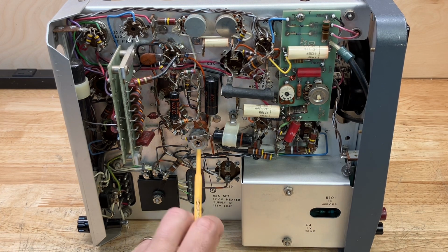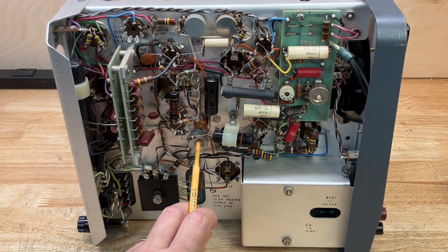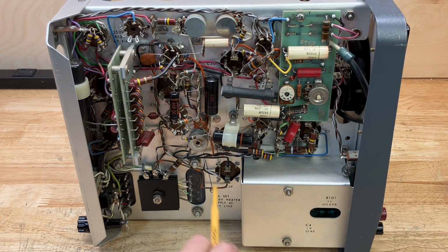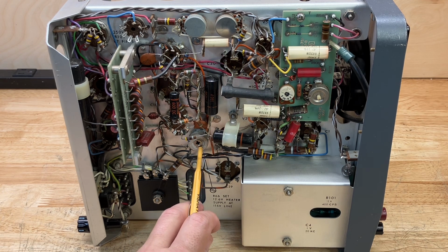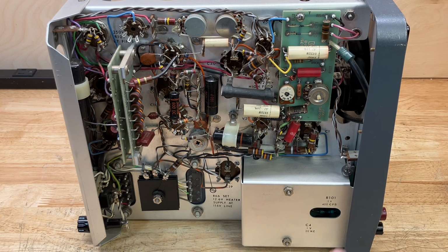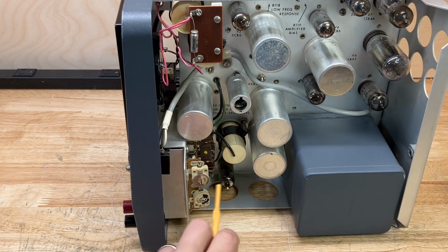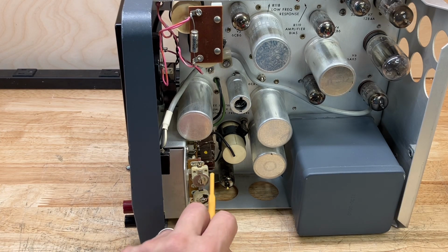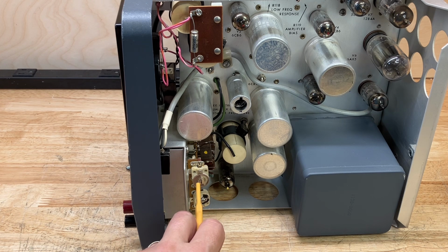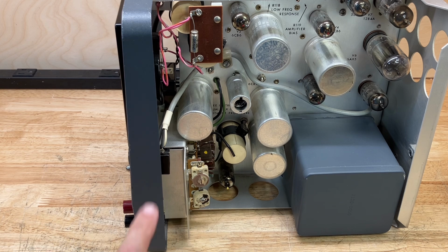Oh, the very first one I forgot to mention is this pot right here. This is the 12.6 volt DC adjustment for the selenium rectifier that controls the filament voltages of those first stages of tubes. This is the 12.6 volt pot that you use to adjust that. So once we've adjusted the 1 volt range on the input attenuator over here, we come back around over here, and we have two more compensation capacitor trimmers over here. This one is for the 3 millivolt range at 4 megahertz. I'm sorry, 3 millivolts at 4 megahertz. And this one down here is for the 10 millivolts at 4 megahertz. We adjust those until we have the correct readings on the instrument for all of those.